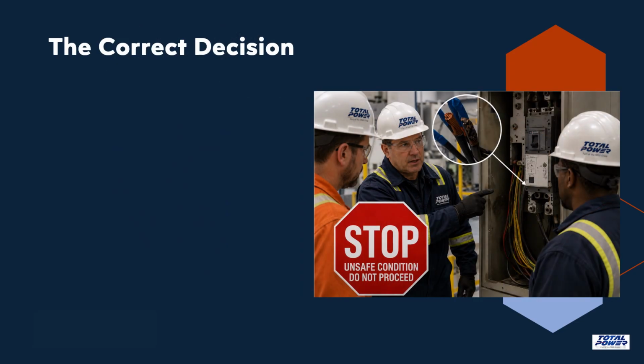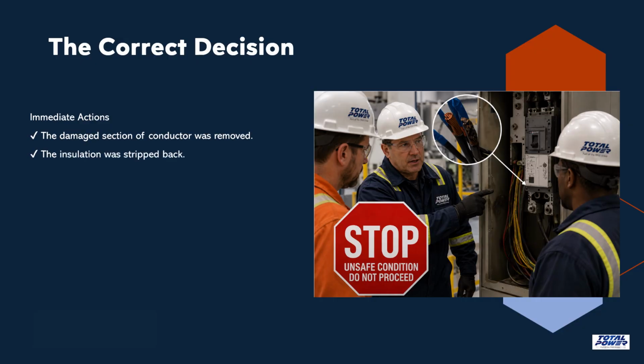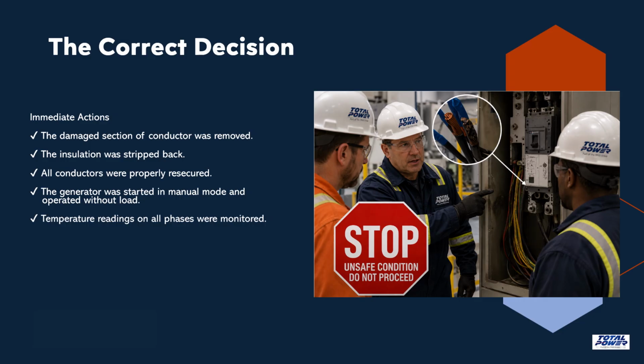The supervisor made the correct decision. Rather than continuing with the load bank test, the work was immediately stopped. Because the cause of the damage was unknown, the crew could not verify the integrity of the generator breaker or determine whether additional hazards existed. The damaged section of conductor was removed. The insulation was stripped back. All conductors were properly resecured. The generator was started in manual mode and operated without load. Temperature readings on all phases were monitored and found to be consistent, indicating no immediate thermal imbalance. The generator was then safely returned to service.